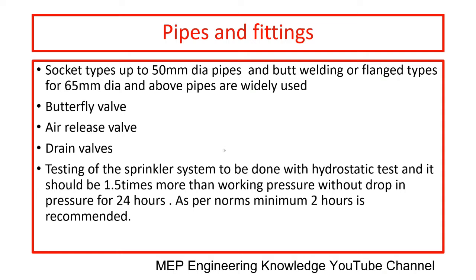Socket type fittings up to 50 mm dia pipes and butt welding or flange type fittings for 65 mm dia and above are widely used. Butterfly valve, air release valve, drain valves are the common fittings used in the sprinkler system. Testing of the sprinkler system is to be done with a hydrostatic test, and it should be 1.5 times the working pressure without drop in the pressure for 24 hours. As per norms, minimum 2 hours is recommended.